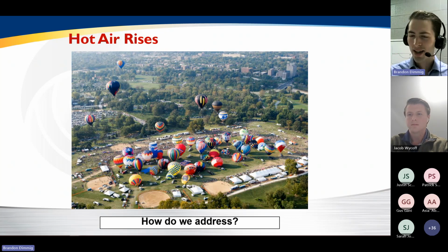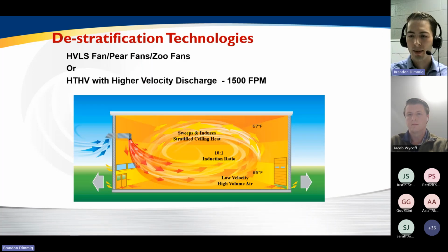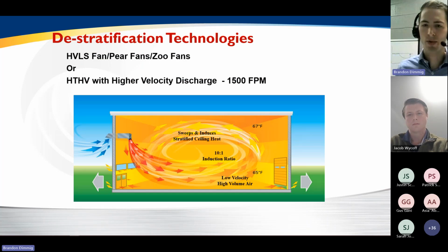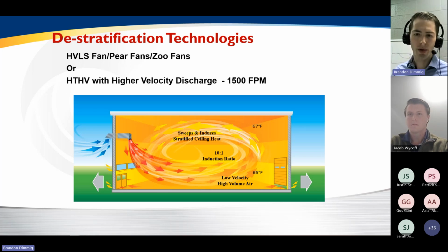Go check it out. But the reality is that hot air rises, and this is nice for hot air balloons, but not so nice in warehouses. Stratification can cause problems, uneven temperatures inside of a facility, and people sometimes use HVLS fans or other kinds of low-cost equipment to overcome that phenomenon. But with the HTHV unit, discharge velocities are actually relatively high, usually in the neighborhood of 1,500 to 2,000 feet per minute. So this has a key benefit as it relates to even temperatures and destratification inside of a facility.